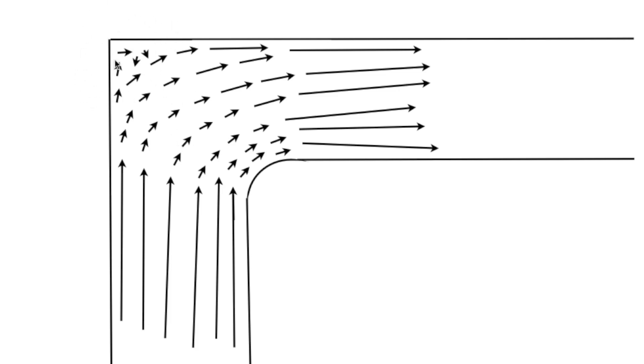Let's take a look up here. This is going to be a highly turbulent area. However, because it's up here... Now on the other one we had a gentle curve here. But the gentle curve doesn't make a huge difference because this turbulence makes this into kind of a gentle curve. The air just kind of comes up. Some of it comes there and starts swirling around. But a lot of it just goes right past and moves out into the ductwork.